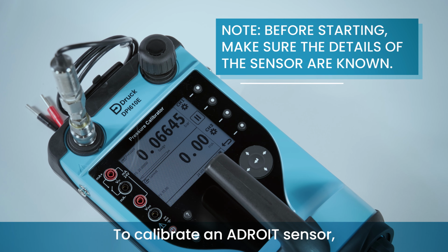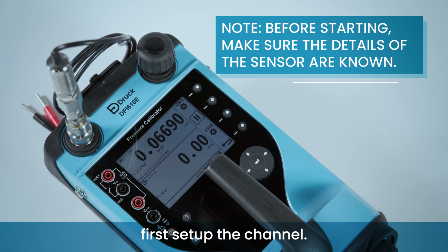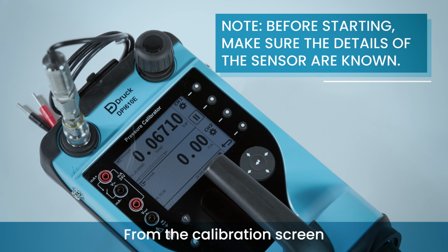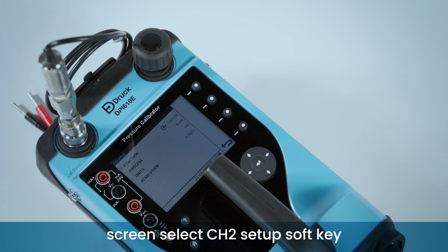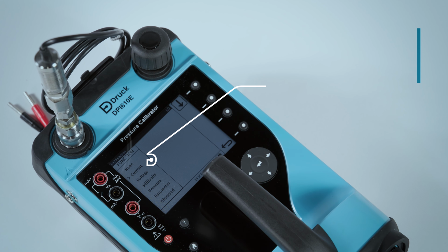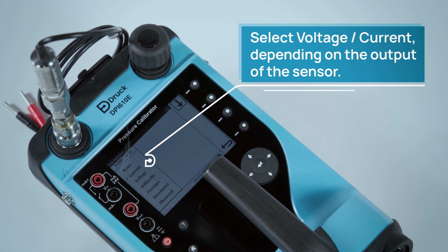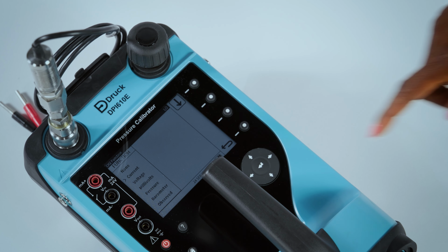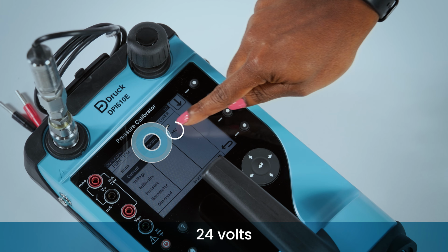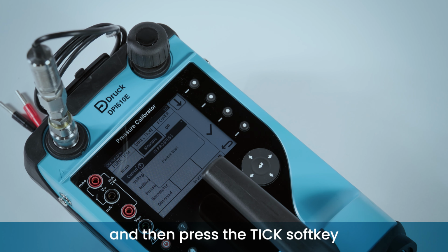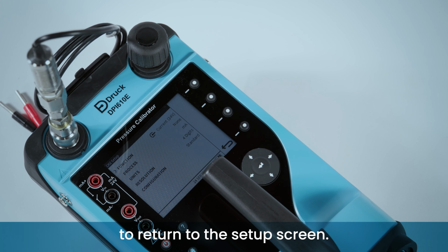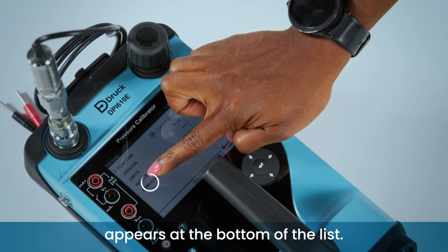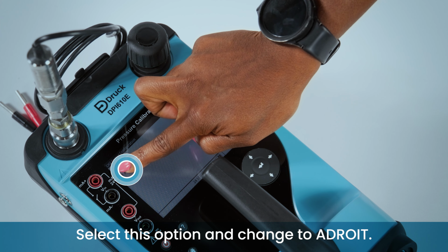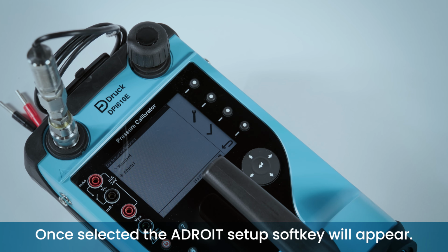To calibrate an ADROIT sensor, first set up the channel. From the calibration screen, select Channel 2 Setup soft key and then Function. Select Measure, 24 volts, and then press the tick soft key to return to the setup screen. The sensor configuration option appears at the bottom of the list. Select this option and change to ADROIT. Once selected, the ADROIT setup soft key will appear.